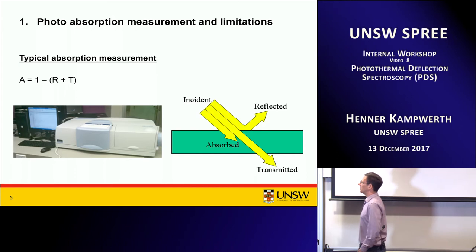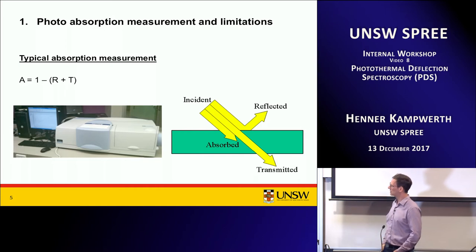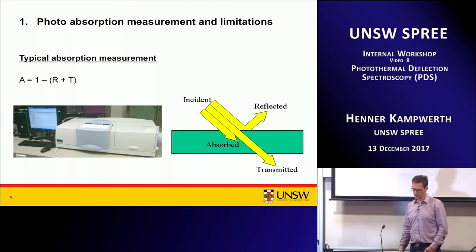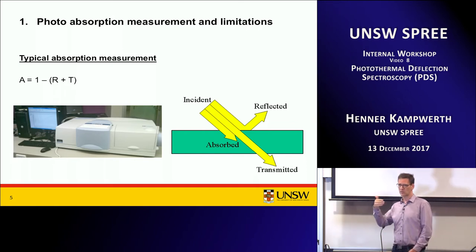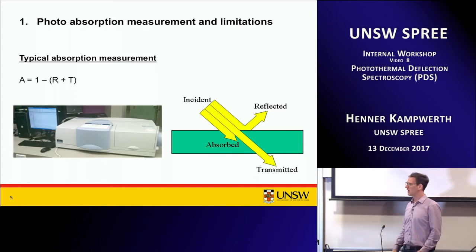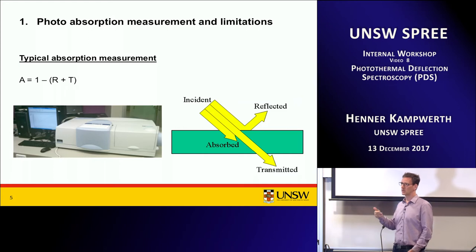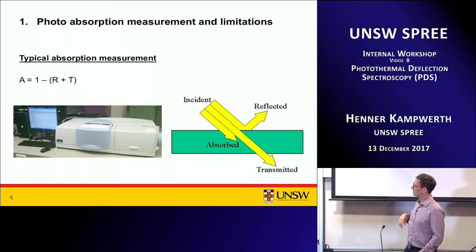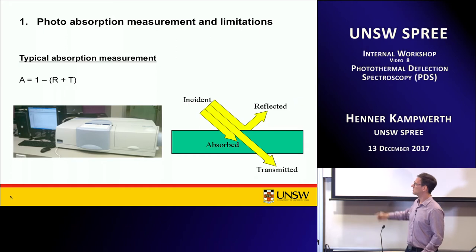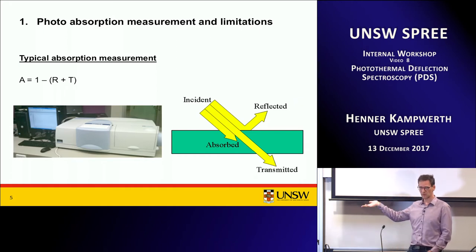Usually we measure absorptance with a reflectance-transmission spectrometer — for example, a Perkin-Elmer, which we have in one of our main characterization rooms. It has a monochromatic light source that shines on the material, measures how much is reflected and how much is transmitted, and the difference between the incident light and the reflected and transmitted is the photons that got stuck in the material — the absorbed amount. So absorptance equals one minus reflectance minus transmission.